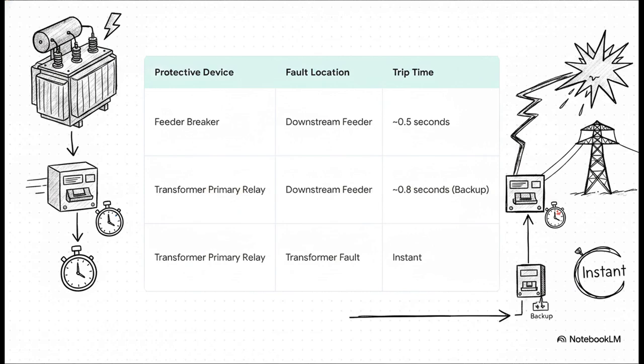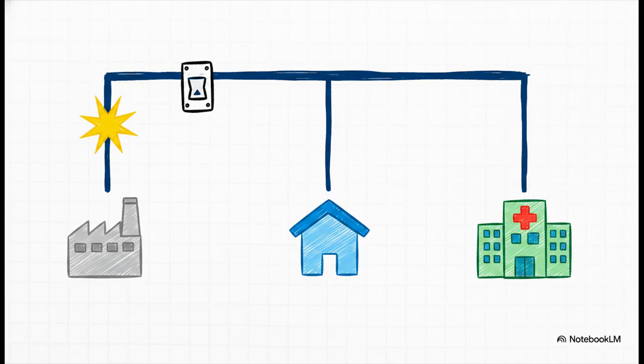If a fault happens on a power line downstream, the circuit breaker for that line is set to trip the fastest, in about half a second. The transformer's own relay actually waits a little longer, around 0.8 seconds. Why the delay? Well, it's pretty smart. It's giving the downstream breaker a chance to clear the fault first. It only acts as a backup, but if the fault is inside the transformer itself, its own protection trips instantly. No waiting. And that, right there, is the whole point.